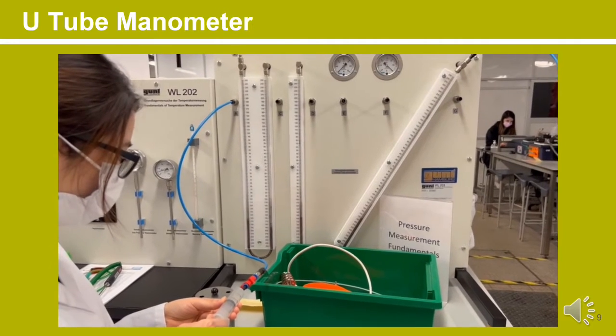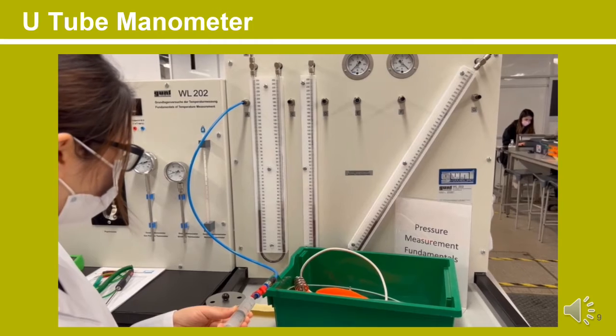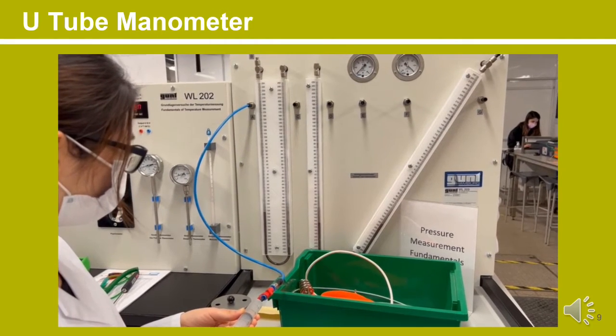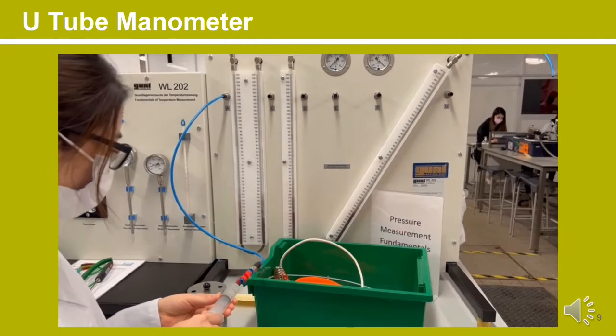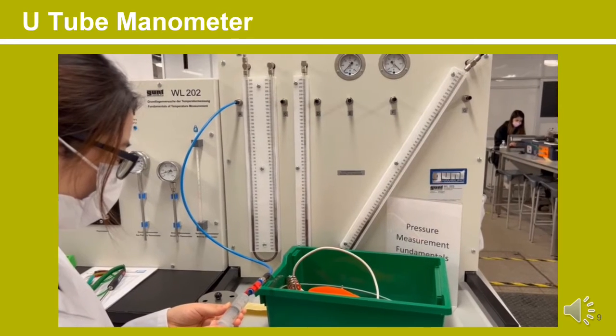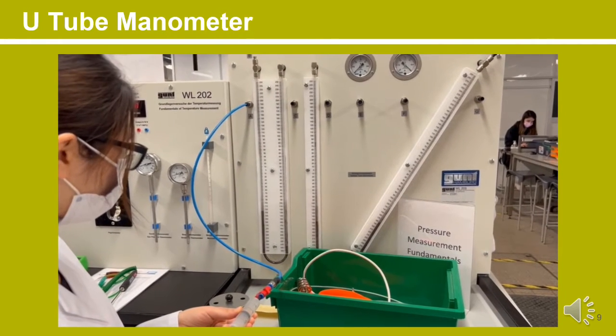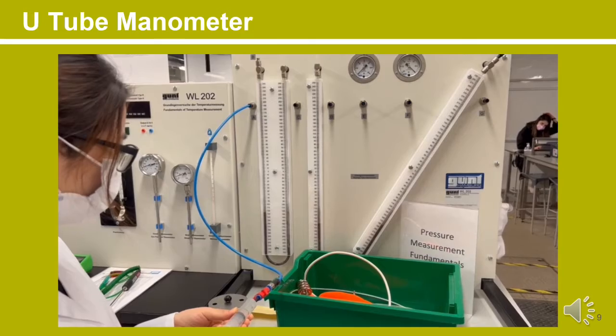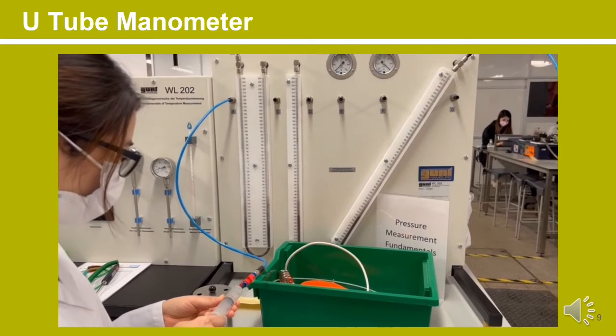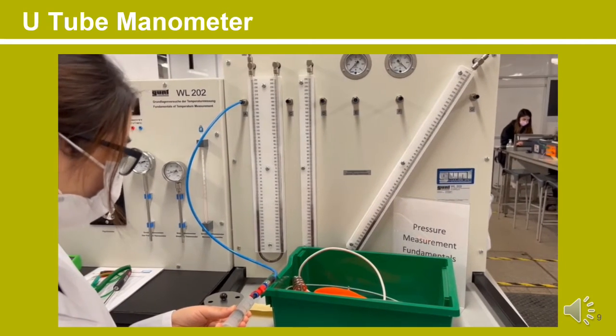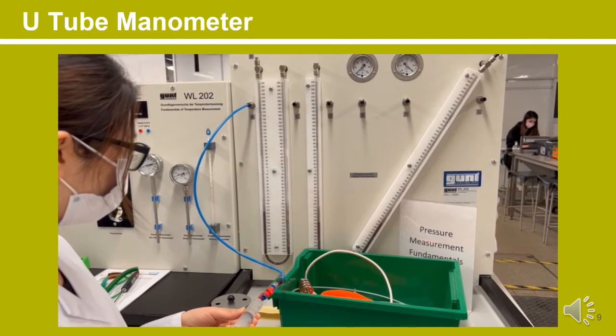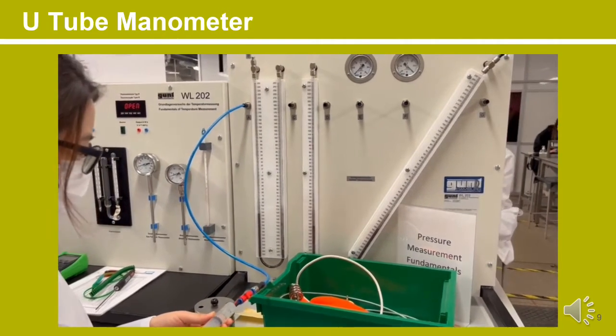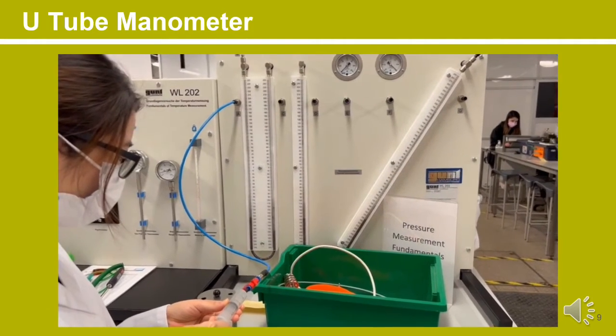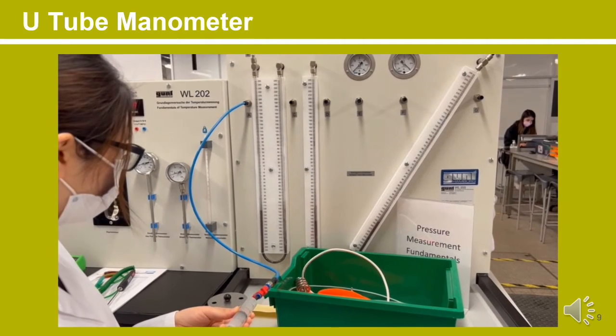To measure the positive pressure, a tube attached to a non-return valve and a syringe was connected to the U-tube manometer. The valve was used to recalibrate. The syringe was then used to push 2 ml of air into the manometer, and the height difference in the liquid was recorded. These values were used to calculate the pressure. It can measure a pressure range from 20 to 300 millibar with uncertainty of positive and negative 0.5 mm.